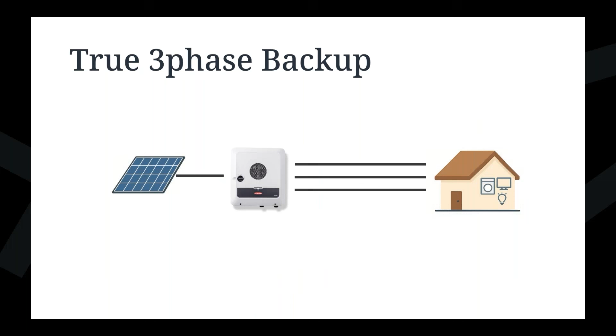Lastly, you can also have more PV capacity. So this is particularly important on single-phase sites. So essentially, grid providers will often limit the maximum total inverter capacity that's allowed on the site. So for example, to 10 kilowatts. Now, with an AC coupled battery, it has that inverter in it, but you're not attaching any panels to it. It's purely just to do the conversion there as the power goes in. But that inverter will also count towards the site's inverter capacity. So say you had a 10 kilowatt inverter. So say our Primo Gen24 Plus 10 kilowatt inverter, you look at its oversizing ratio. So for that inverter, it's 150%, meaning it's a 10 kilowatt inverter. So 150%, that'd be 15. You can have 15 kilowatts worth of PV attached to it. So 15 kilowatts worth of panels.